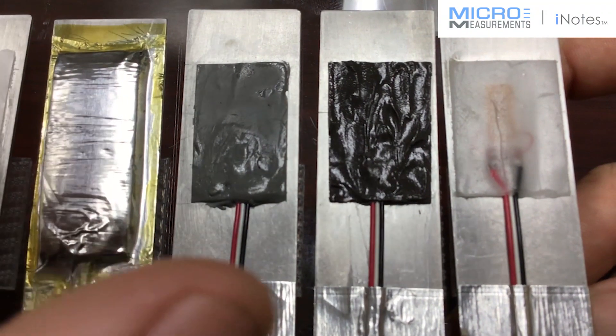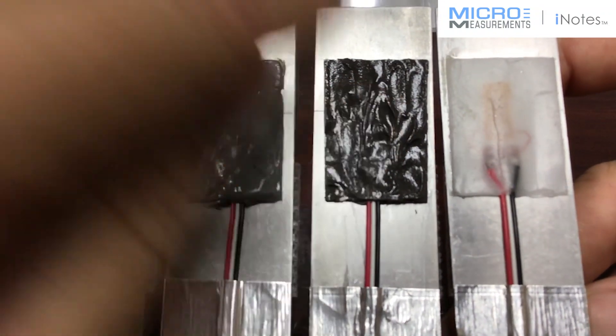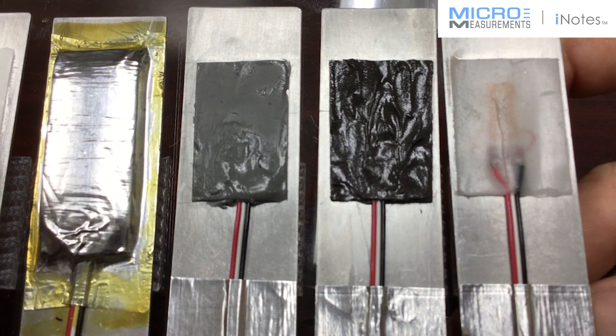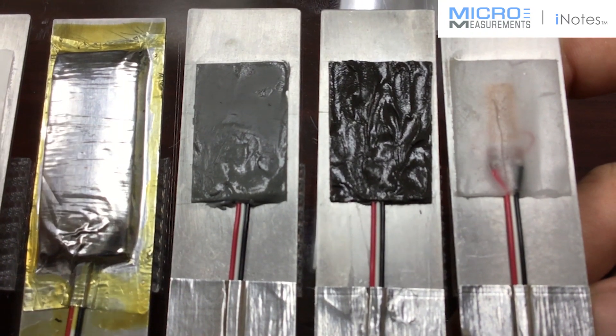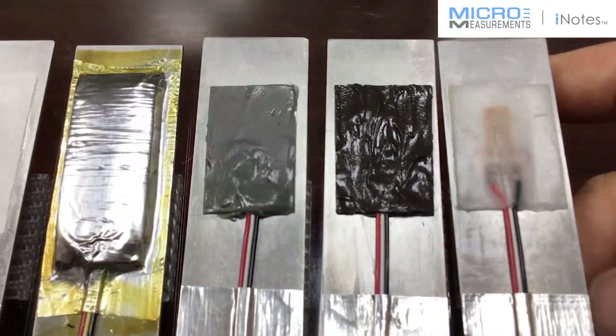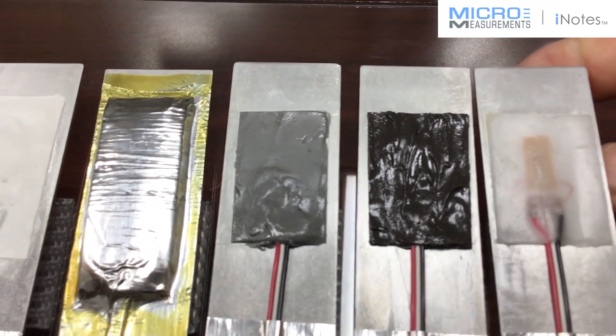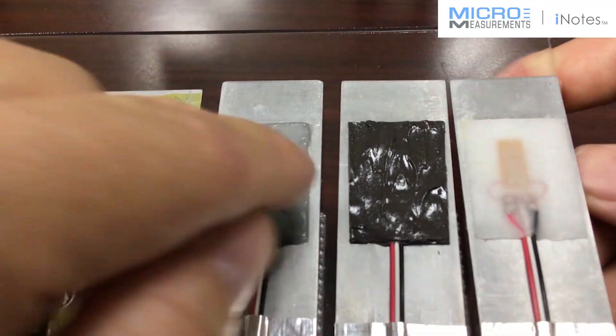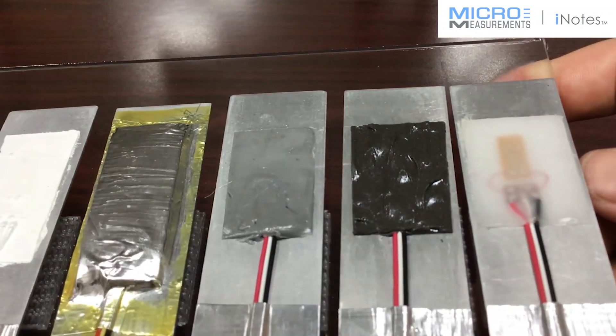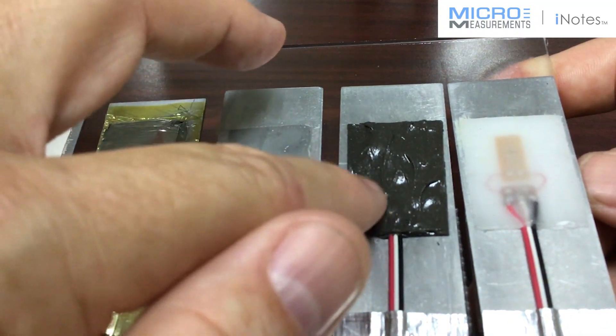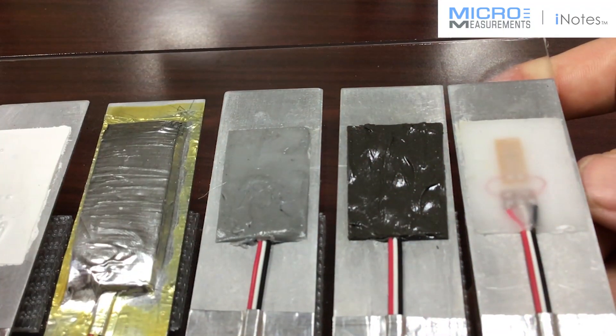Really good in terms of mechanical protection. You could just about hit this thing with a hammer and the gauge would be protected underneath. But also very good chemical and moisture barrier too. So when you're looking for an environmental coating that cures at room temperature and maybe you need some mechanical protection and moisture protection, this is a very good coating system for protecting the gauges in those types of environments.